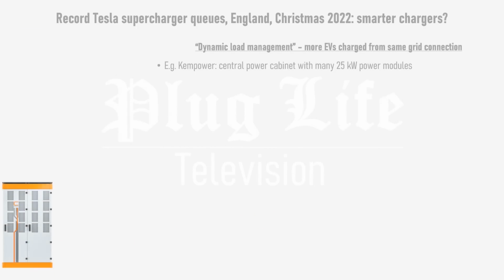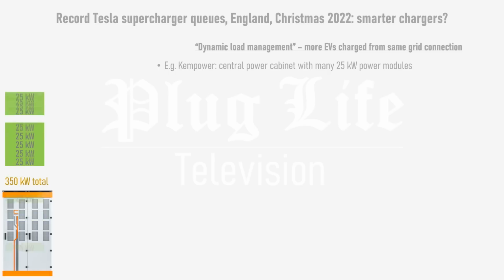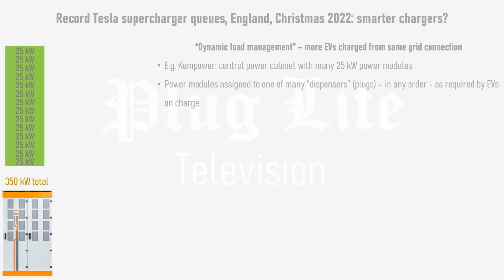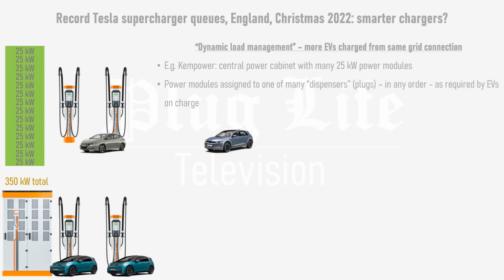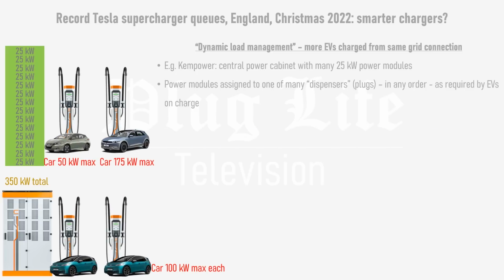This is where dynamic load management comes in. One of the best examples is Kempower's system, which features a central power cabinet full of 25 kilowatt power modules that add up to whatever capacity you need for your charging hub. In this case, we have 350 kilowatts worth of power modules, making use of the same grid capacity as the 350 kilowatt standalone charger. The power cabinet assigns the power modules to one of many dispensers, or charging plugs, in any order, depending on the power that each car needs.